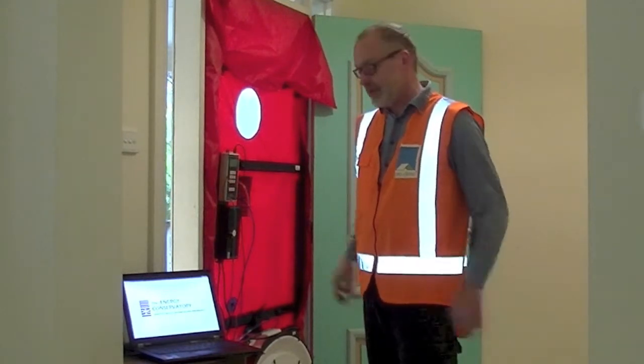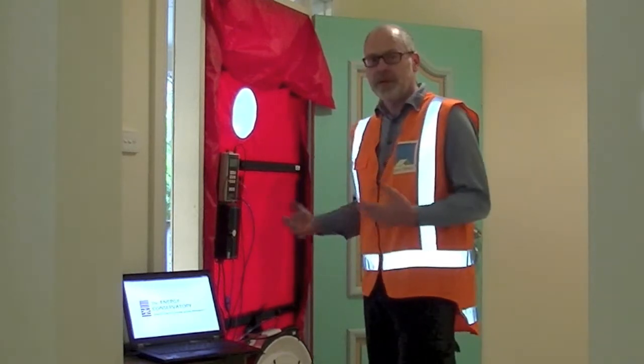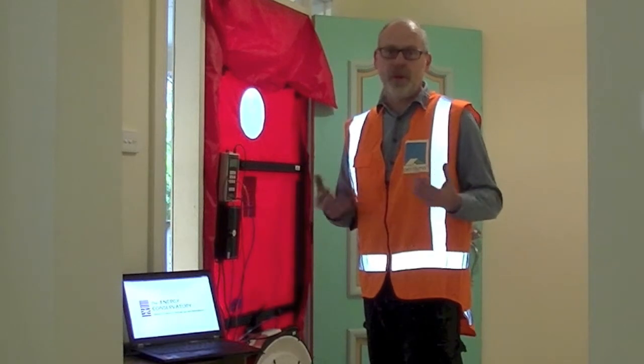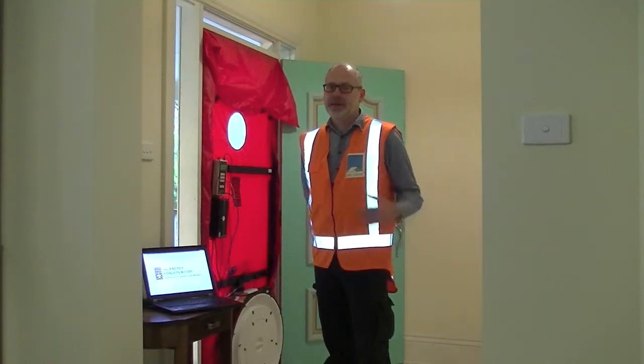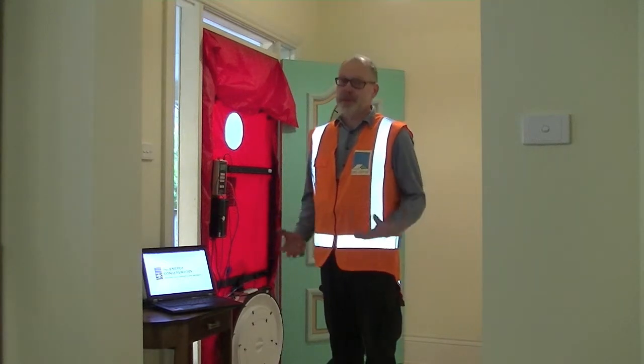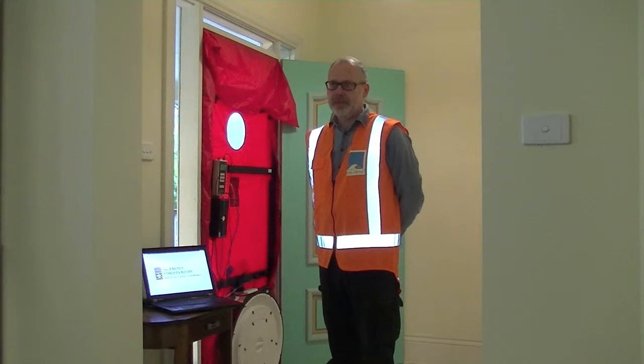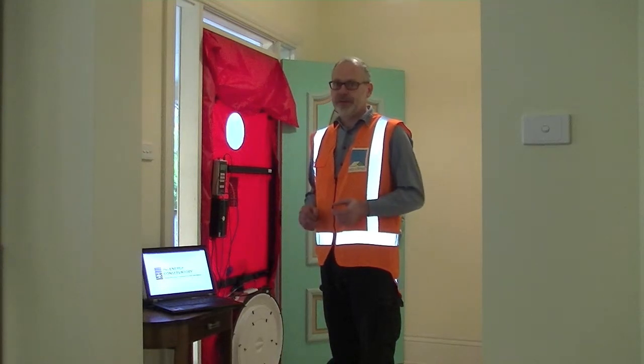What we are looking for is to get a result on what the air infiltration is via this device, to give us an idea of where there are deficiencies and where we can make improvements in terms of the energy efficiency of this house. In terms of air infiltration and leakage into Australian buildings, it's quite typical when we do blower door testing that we will get something typically 10 to 15 air changes at 50 pascals.